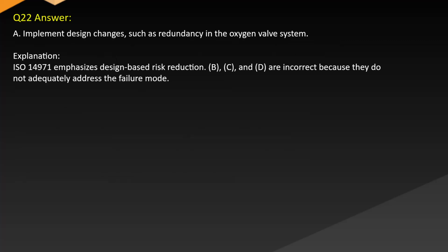Answer A. Implement design changes such as redundancy in the oxygen valve system. Explanation: ISO 14971 emphasizes design-based risk reduction. B, C, and D are incorrect because they do not adequately address the failure mode.